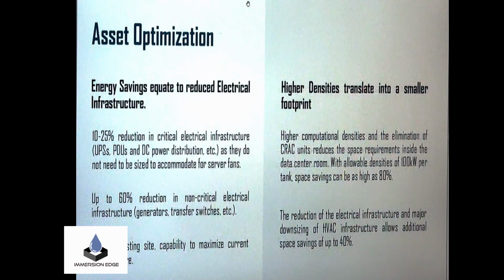All these higher densities translate into smaller footprints, so we have up to 100 kW per tank, and that space savings equates to savings as high as 80%. The reduction of electrical infrastructure and major downsizing of your HVAC equipment allows additional savings of up to 40%. So this is why it starts to make sense that this is a really great application - maybe not for all edge data centers, but for at least a portion of edge data center applications for sure.